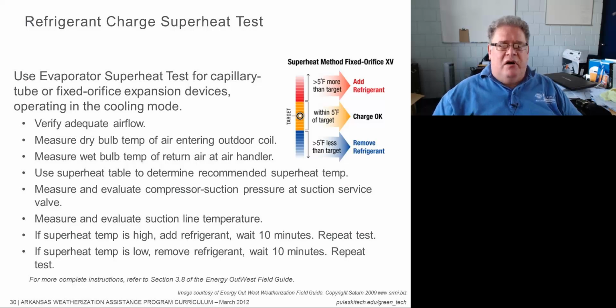Okay, so moving on, you can use the superheat table on the unit to determine a recommended superheat temperature. You want to measure and evaluate compressor suction pressure at the suction service valve and measure and evaluate the suction line temperature. If your superheat temp is too high, you're going to add refrigerant, wait 10 minutes, repeat the test. If it's too low, remove refrigerant, wait 10 minutes, repeat the test. This is if you can't vacuum down the entire system and put it back. If you want complete instructions on this, you can look in the Energy Out West field guide. It's a pretty darn good field guide. I think section 3.8 goes over all this.